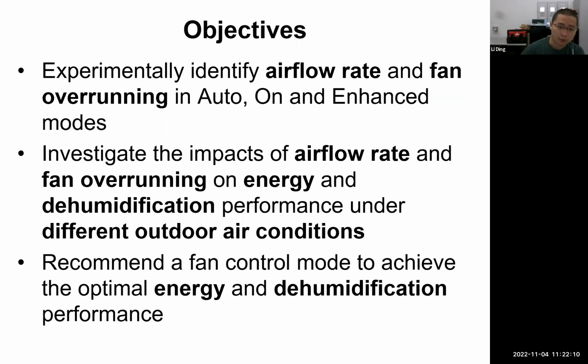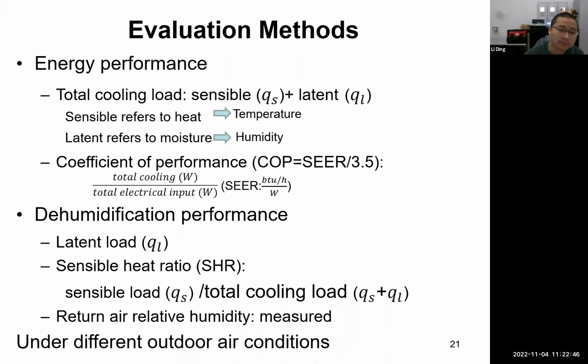Then we can point out our objectives. First, experimentally identify the airflow rate and the fan overrunning in on and enhanced mode. Second, investigate the impacts of airflow rate and fan overrunning on energy and dehumidification performance under different outdoor air conditions. Last, recommend a fan control mode to achieve the optimal energy and dehumidification performance.